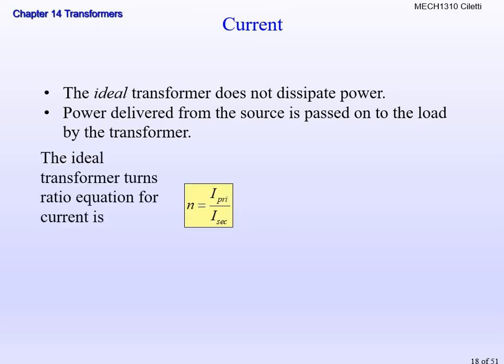Before, when we talked about turns ratios, I said when we're dealing with voltage it's always secondary over primary. Here's the caveat: when we're dealing with current, the turns ratio swaps, it's primary over secondary. You have to remember this when doing the turns ratio calculation, since it's the opposite of what it is with voltage.